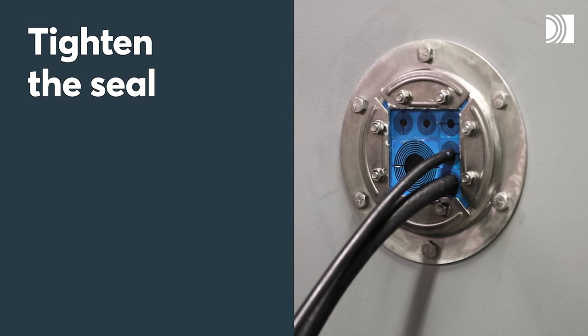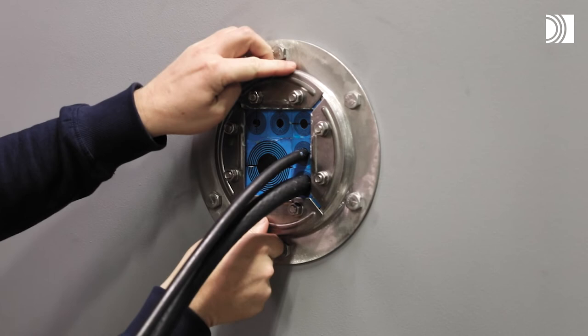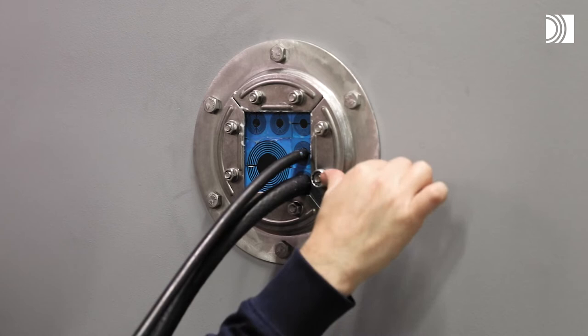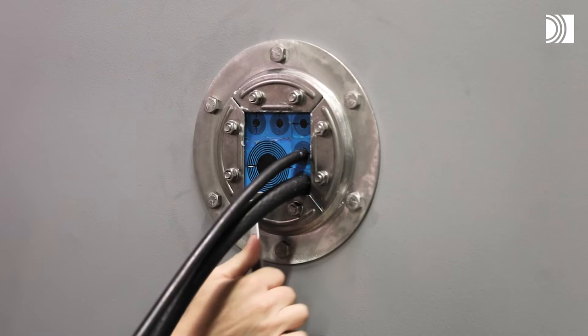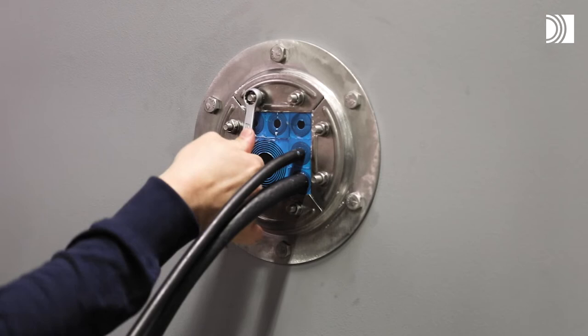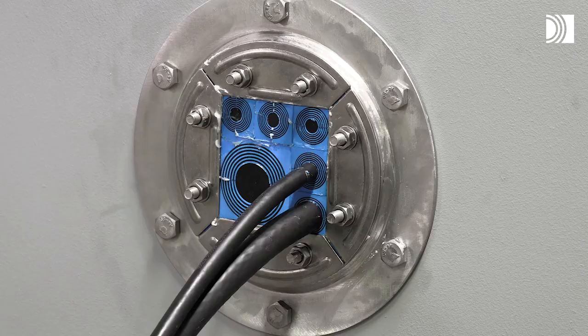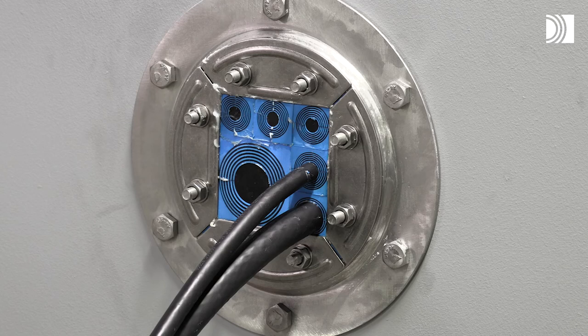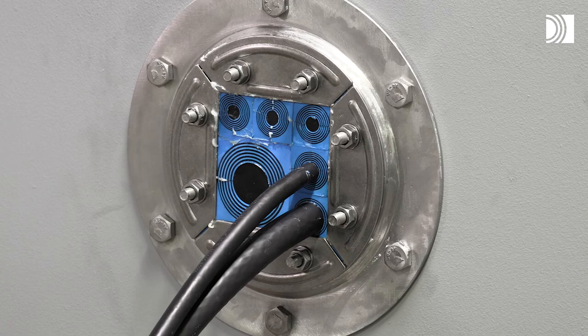Tighten the seal. Push the front fittings back towards the center. Tighten the nuts crosswise in small steps. Signs of good compression are the bolts are tightened similarly, no excessive lubricant is visible directly after installation. The rubber surfaces bulge and show convexity.